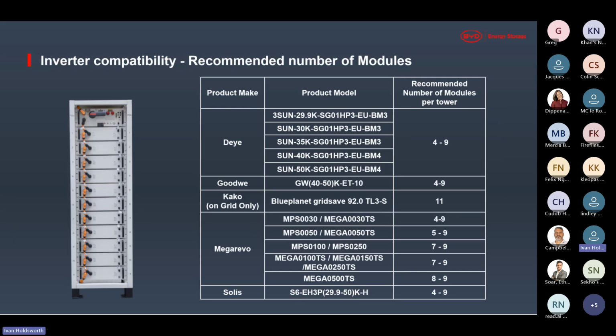Here we can see the compatible inverter list and the number of modules that you can use. For example, on the Deye, it's from like the 30 to the 50 range, 30 kilowatt to 50 kilowatt range. You can use between 4 and 9 modules. On your Deye 80 kilowatt, which is in the process of being tested as compatible, you'll probably be able to use up to 11 modules because the operating voltage of the Deye 80 is larger, but that's still in testing.